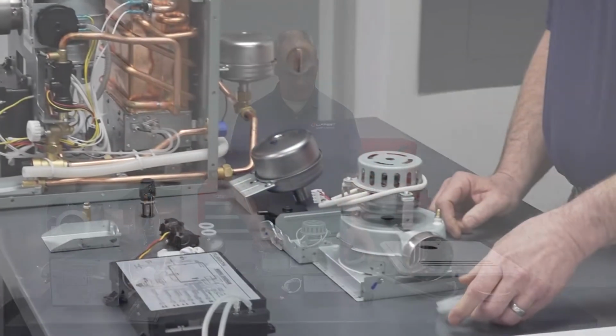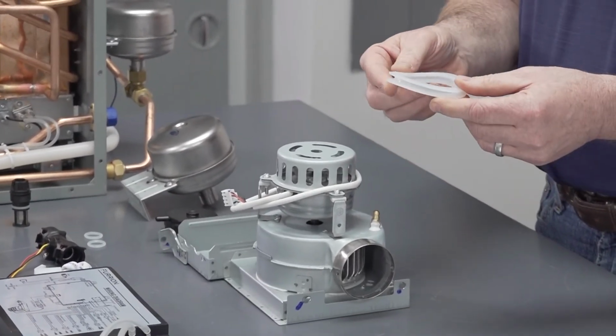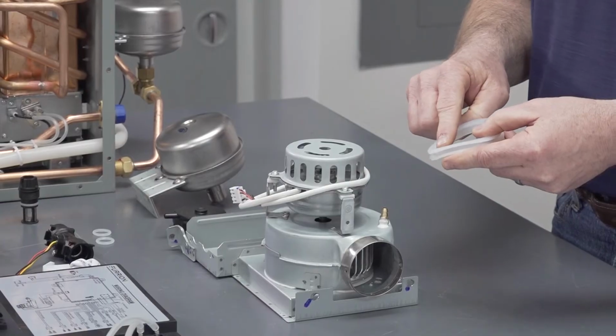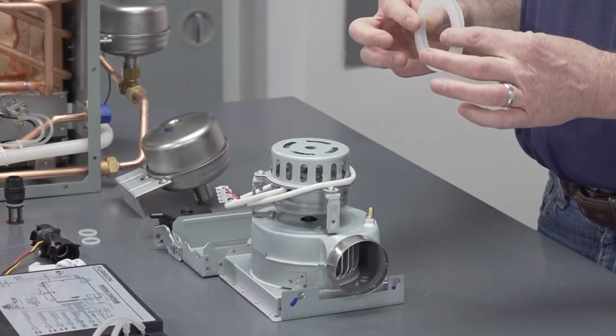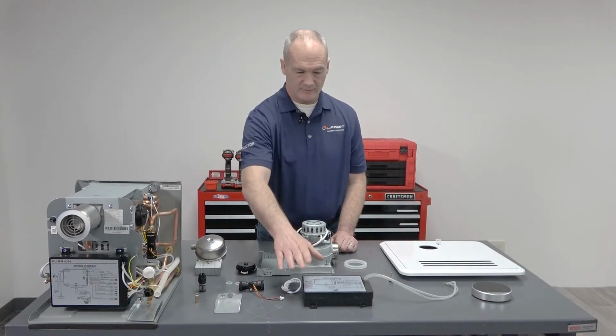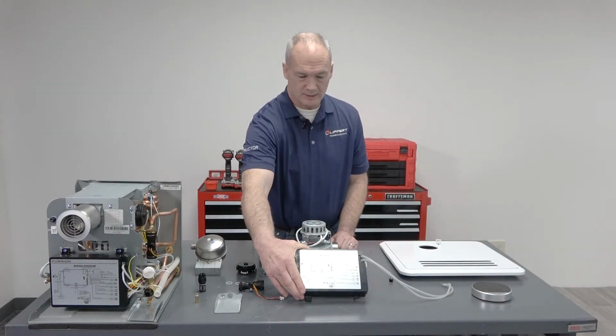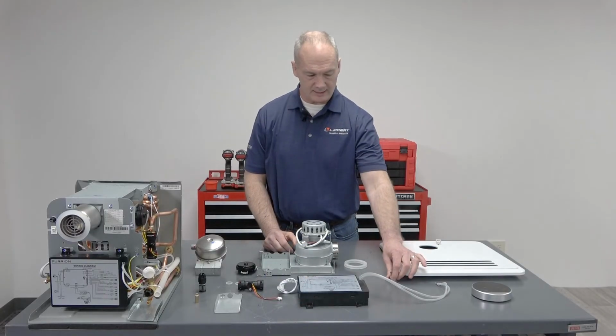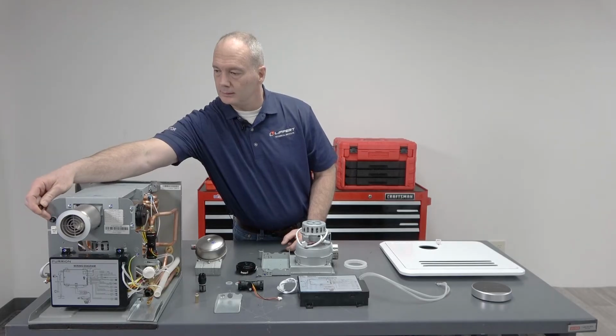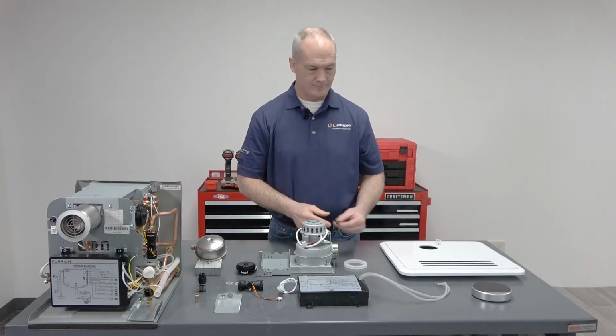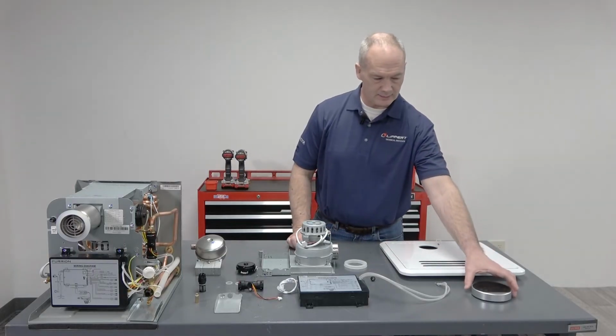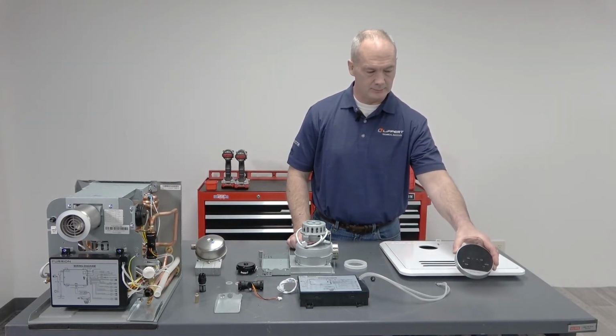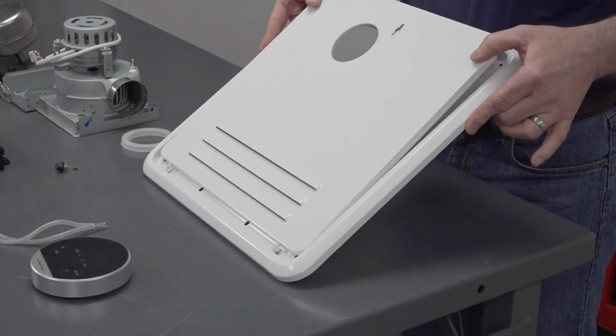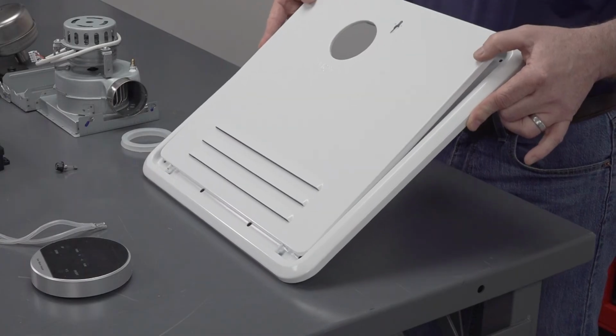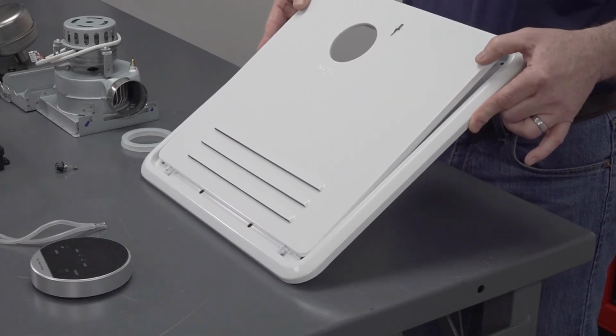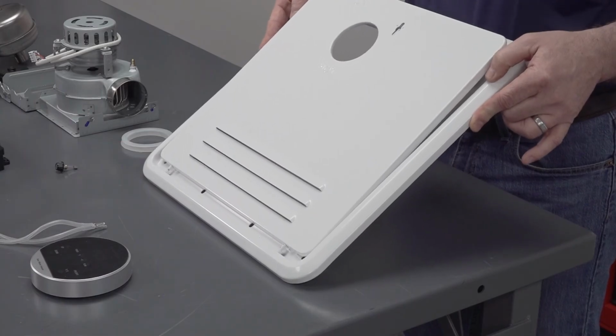On the flue duct assembly, you have a flue duct seal, and there is an "inside" stamped on the seal itself, so you always know that it goes on the inside of the unit. Then we have our control panel. This is the brains of the unit. We talked about that. And a 10 amp fuse that goes right here. Next, we have our thermostat. You can install that inside the unit. These doors come in 3 different sizes, depending upon if you're replacing a bigger water tank type water heater. We have 3 different sizes for retrofitting.